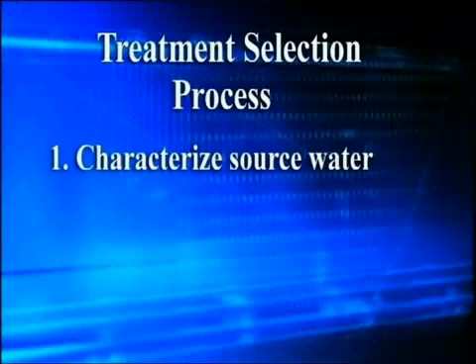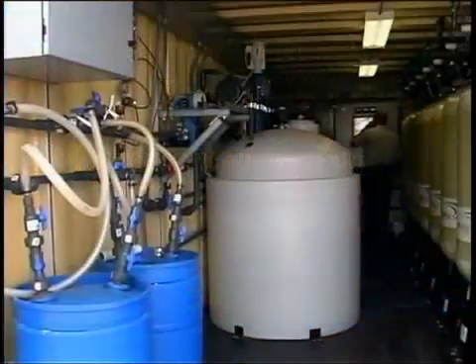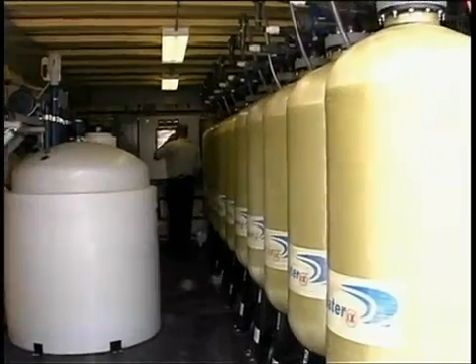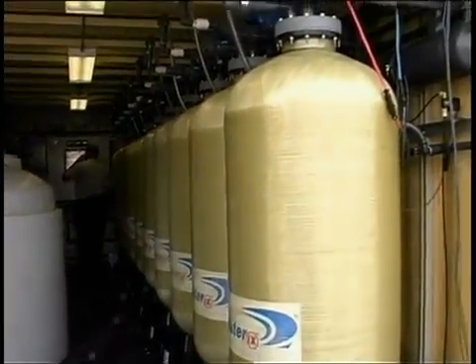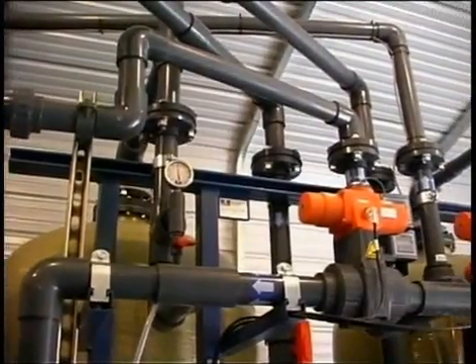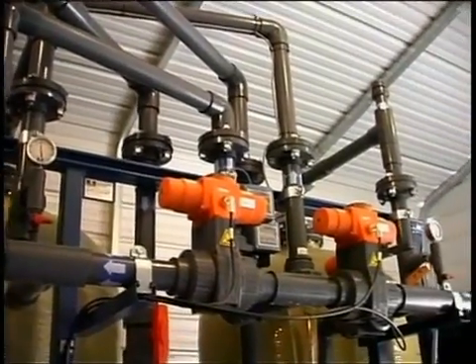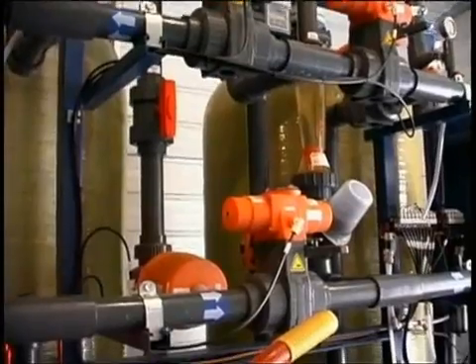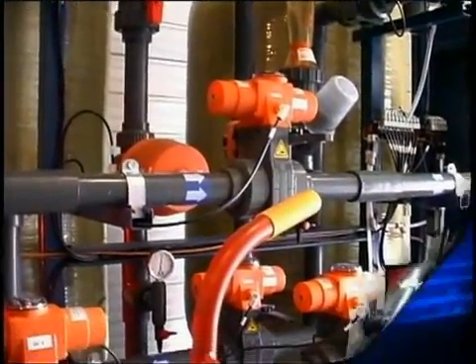The first step is to characterize your source water to determine if co-occurring contaminants present treatment limitations. Some of the arsenic treatment technologies currently available, such as adsorptive media processes and ion exchange, are sensitive to competing contaminants present in the source water. The decision trees in the handbook provide more detailed information on the significance of source water characteristics.